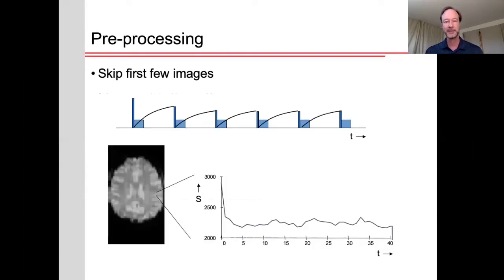The first is to skip the first few images. Now why do we do that? Well the first image that you acquire, typically no other image has been acquired for a period of time before that, however in all the subsequent images the volume has been excited a TR beforehand. And therefore with the typical TRs that we're using for imaging studies about one or two seconds, the magnetization has not fully recovered compared to what was the case in the first image. As a result we see brighter signal in the first few time points before we reach this steady state. So the solution is to simply ignore or remove those first few images. Now the scanner can actually do that for you, you can prescribe some dummy acquisitions, however I prefer to acquire this data and then you can remove it yourself because there is actually some interesting information that could make use of if one wanted to.